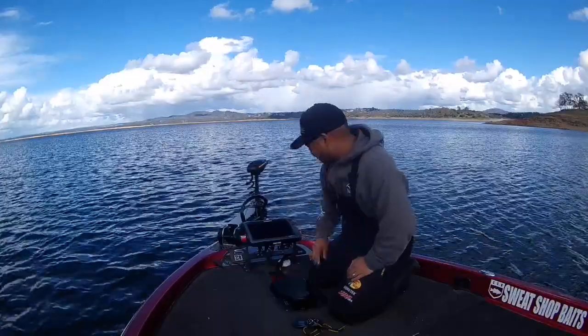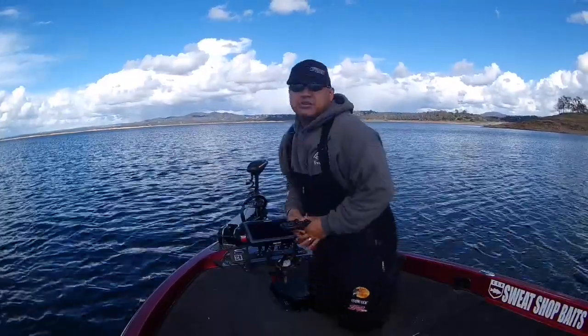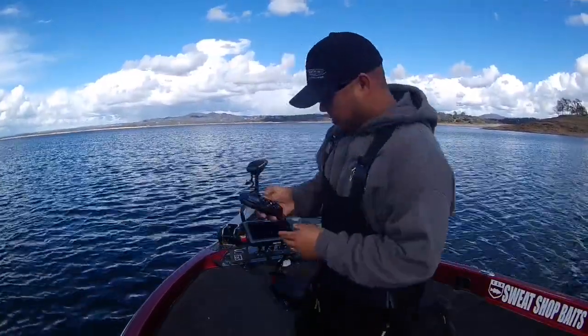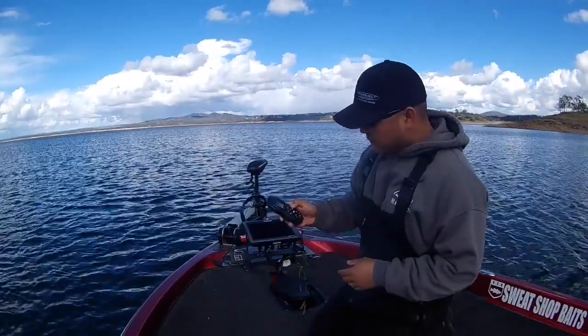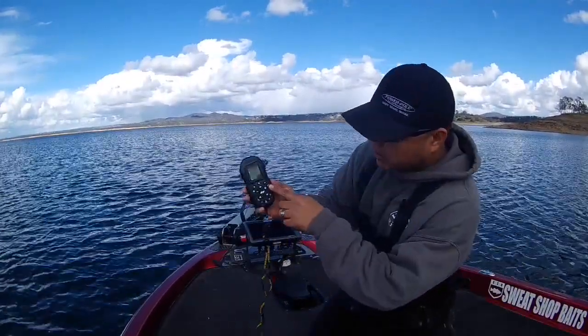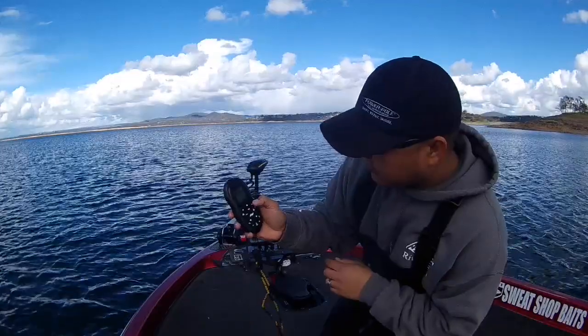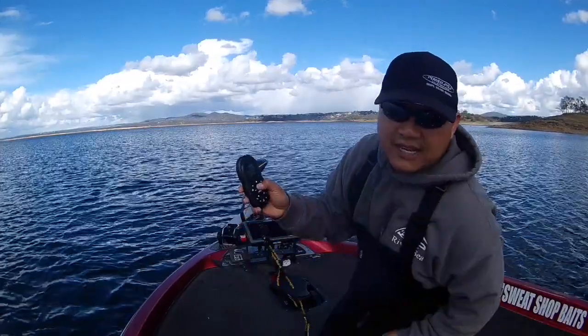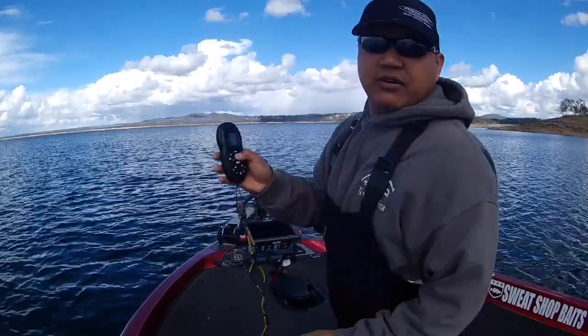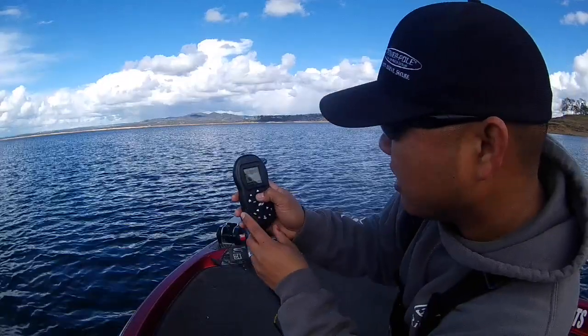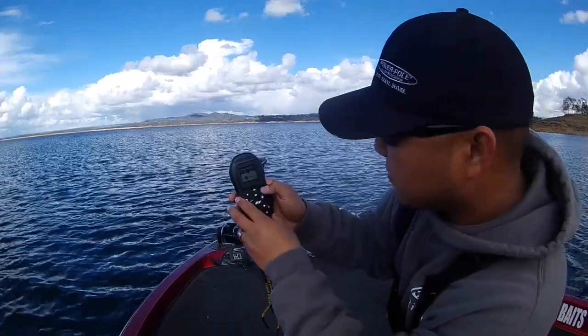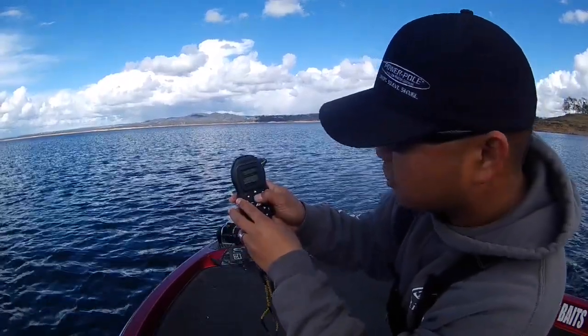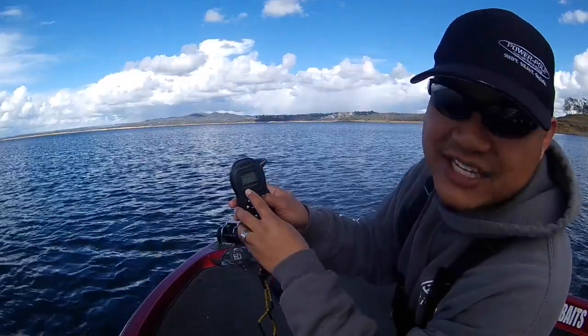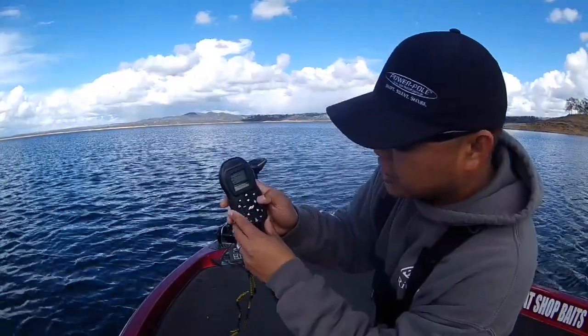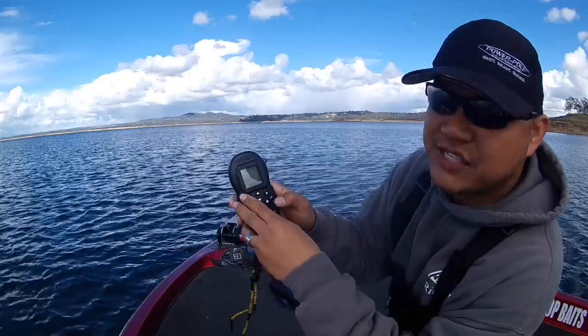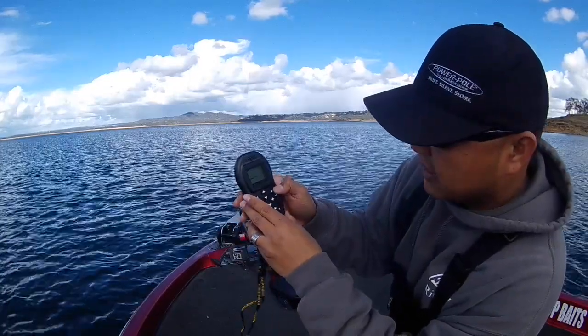That's step one. Step two: take your remote, power it on using the check mark, hit OK. Use the up and down buttons to go to Options, System, select it, scroll down to Sensor Cal, hit the check mark for OK. It'll say press start, so hit the start button.